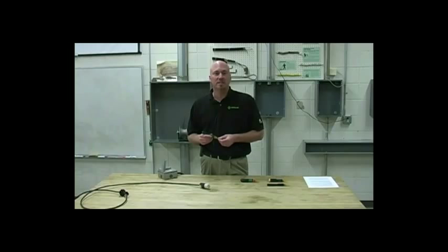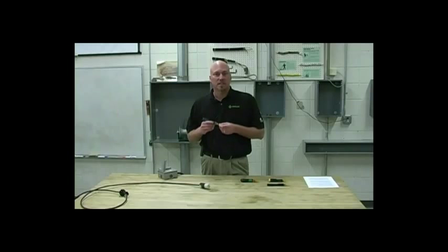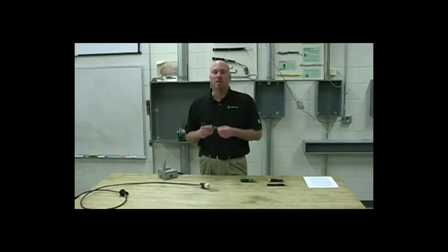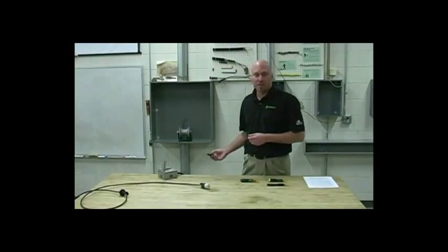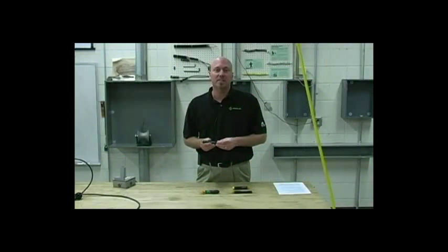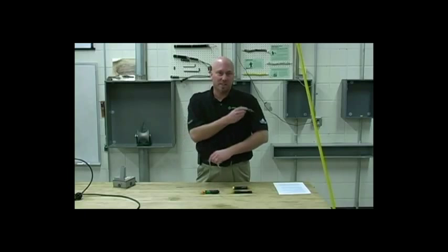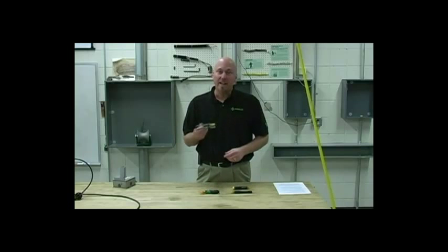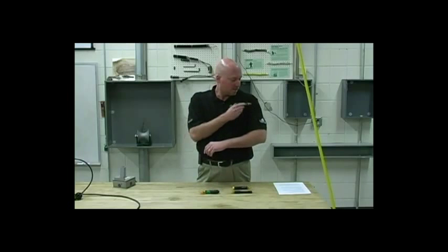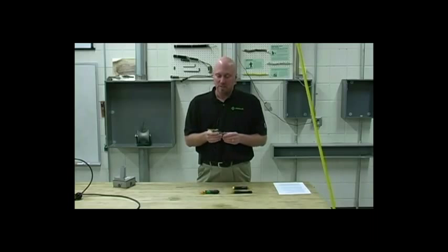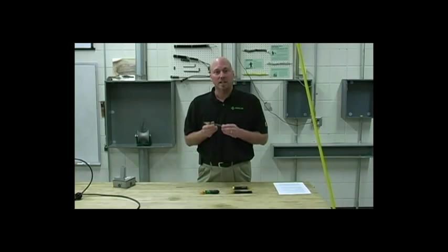The GT11 cannot detect AC voltage in cable through a metallic shield such as armored cable or metallic conduit. Like any non-contact voltage tester, the GT11 can be sensitive to static electricity. A handy way to check the batteries of the unit is to rub it against your shoulder and see that you get the LED lights and the beeping.